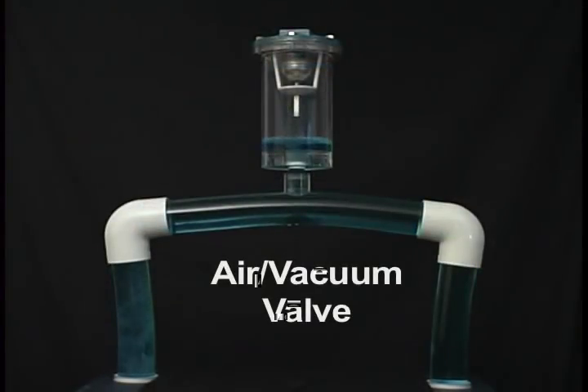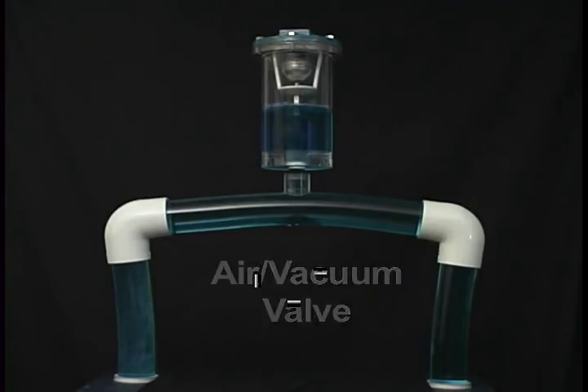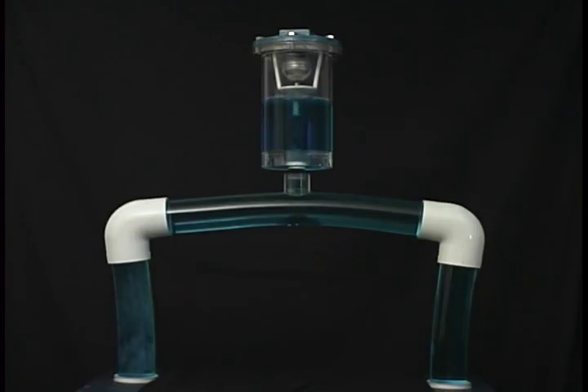We've seen how an air release valve will vent air at system high points, but air release valves will not admit large quantities of air or allow air in for vacuum protection. For that, you need an air vacuum valve like the one shown here. Air vacuum valves, sometimes referred to as large orifice valves, are used to exhaust large quantities of air upon system startup, as well as allowing air to re-enter the line upon system shutdown or system failure.